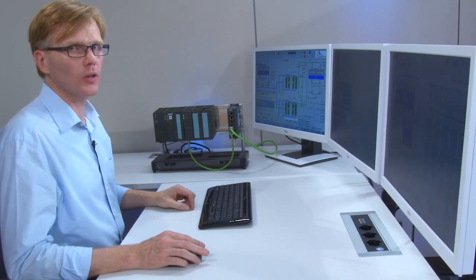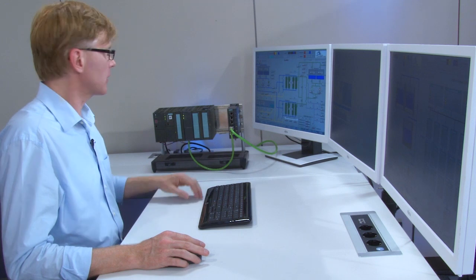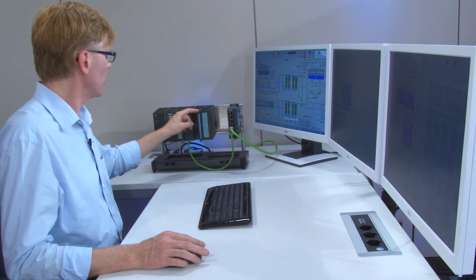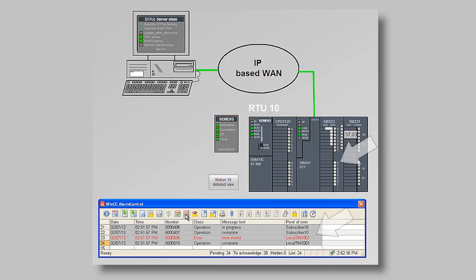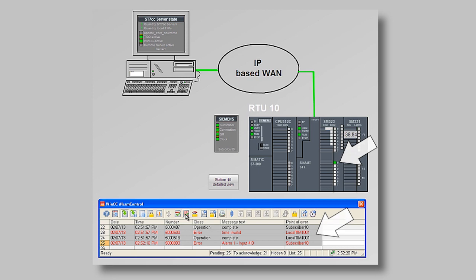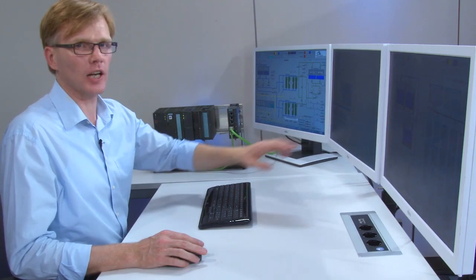Now we will generate an alarm on the digital input module, and we see the alarm is displayed immediately on the control center by a change in color and an alarm message appears in the alarm log.